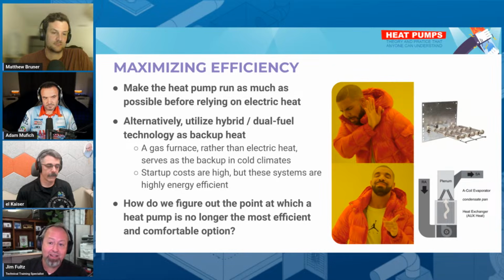Well, and calculate that balance point for capacity, for how much that heat pump can do, and when it's going to drop off. It's that capacity balance point. I know you have a thermal balance point, I think is maybe the more proper term, but capacity makes more sense to me. Yeah. It gives that definition rather than the energy savings balance point, which we discussed earlier.